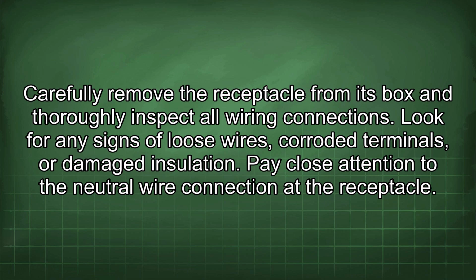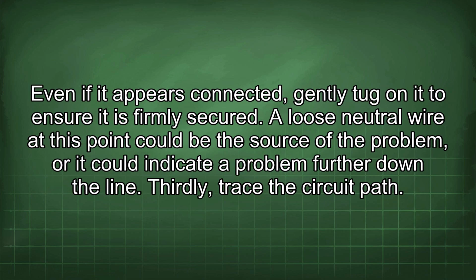Pay close attention to the neutral wire connection at the receptacle. Even if it appears connected, gently tug on it to ensure it is firmly secured. A loose neutral wire at this point could be the source of the problem, or it could indicate a problem further down the line. Thirdly, trace the circuit path.